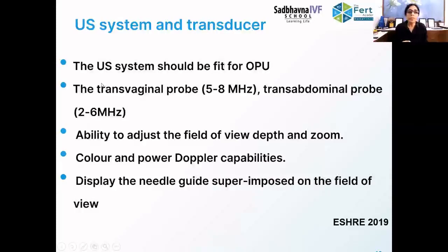The ultrasound system which we need should be fit for ovum pickup, meaning it has a transvaginal probe with this frequency. A transabdominal probe should also be available. The machine should have the ability to adjust the field of view, the depth and zooming options. Color and power Doppler capabilities should be there because at times when you are doubtful, you just switch on the color and it becomes simpler to know where the vessel is and where the follicles are.